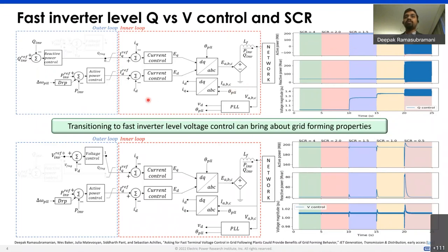But what we observe is, if in the same structure we keep everything the same in the inner loop, but all that we change is we go from this Q control to a V control in the inner loop, then transitioning to this fast inverter level voltage control actually makes the resource stable in very low short circuit ratios, and can even be stable when you have only 100% inverters.